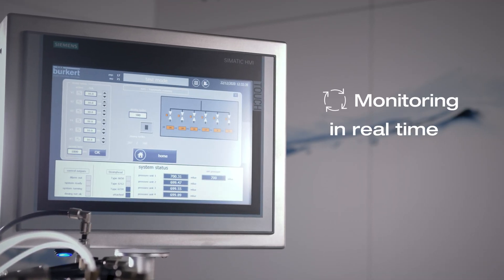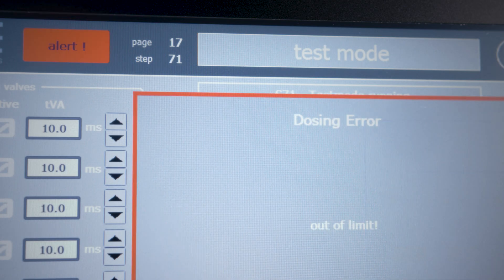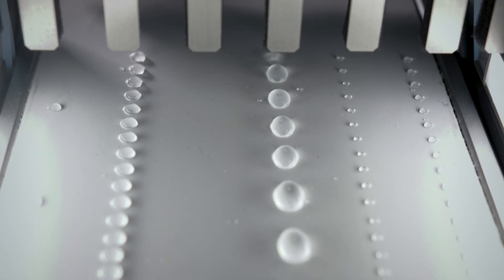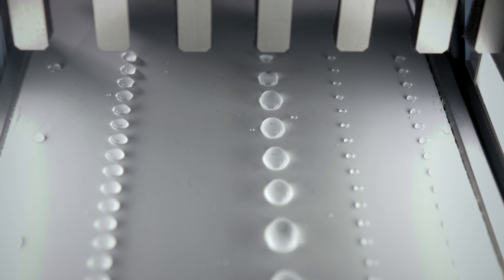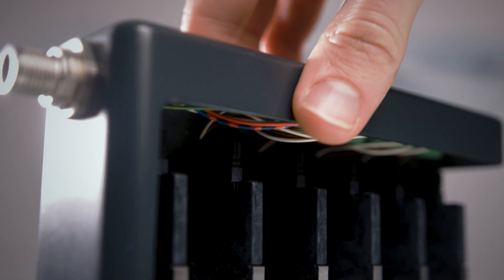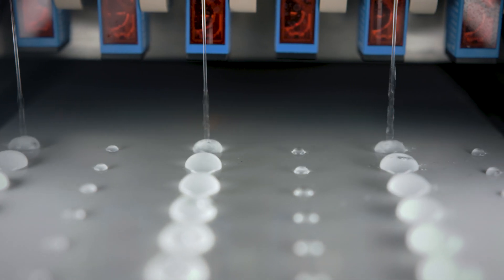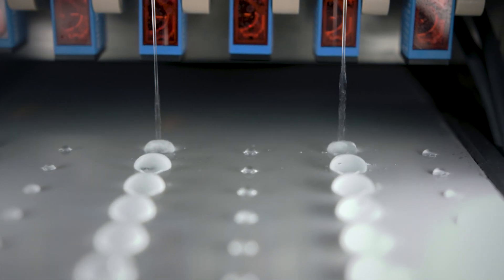In order to permanently monitor the process, the switching point can be detected in real-time and an error can be immediately displayed by the digital communication interface. This way, for example, valves can be replaced directly, sparing you the time and resource-consuming production of faulty oligonucleotides.